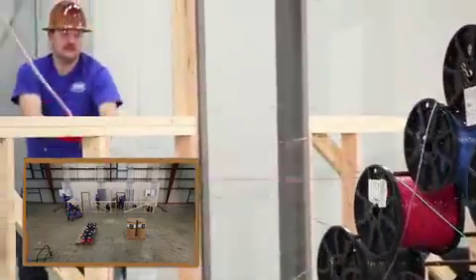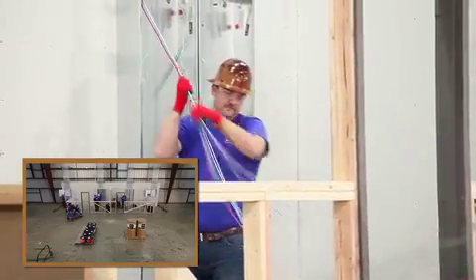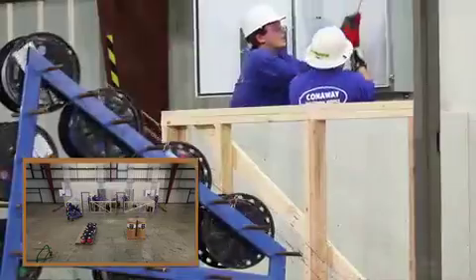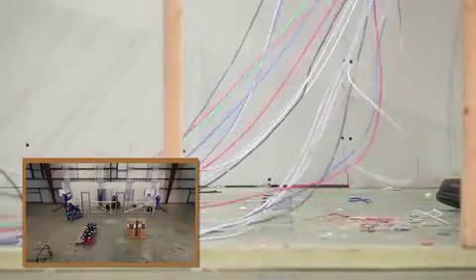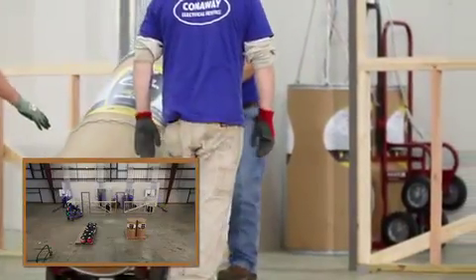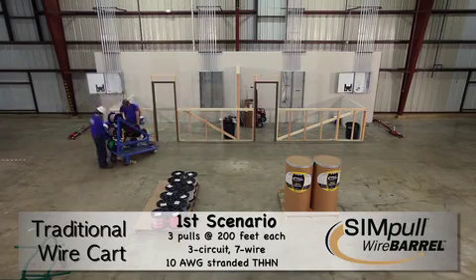Notice the wire cart is too large and bulky to fit inside the electrical room. This leaves a lot of space between the wire and the feed conduit, which can lead to wire dragging across the floor. This can increase the risk of damage to the wire and the likelihood of tangles in the parallel. Southwire's SIMpull WireBARREL and SIMpull BARREL truck products are designed to fit in tight spaces, like these 30-inch doorways, allowing the wire to be located closer to the feed conduit.